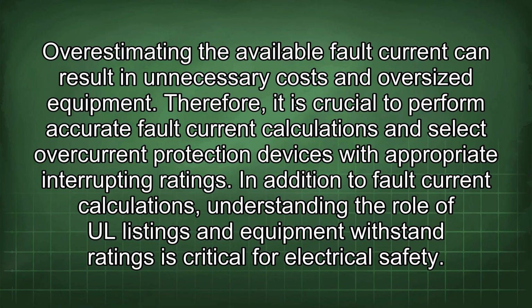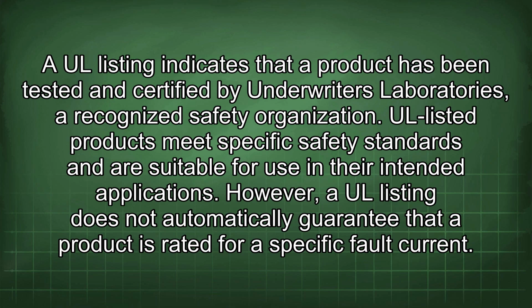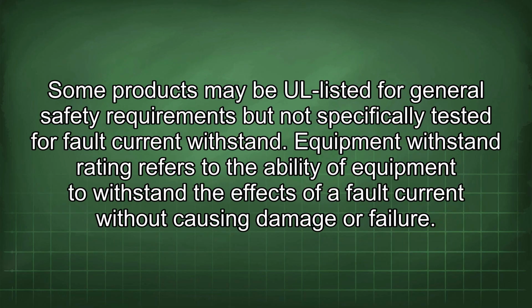In addition to fault current calculations, understanding the role of UL listings and equipment withstand ratings is critical for electrical safety. A UL listing indicates that a product has been tested and certified by Underwriters Laboratories, a recognized safety organization. UL-listed products meet specific safety standards and are suitable for use in their intended applications. However, a UL listing does not automatically guarantee that a product is rated for a specific fault current. Some products may be UL listed for general safety requirements but not specifically tested for fault current withstand.